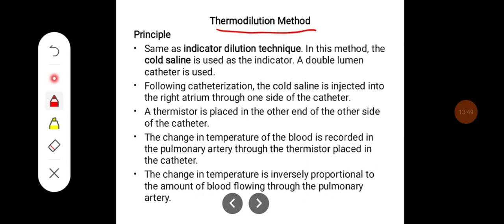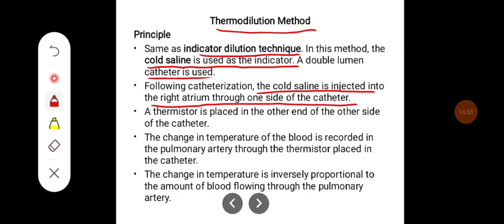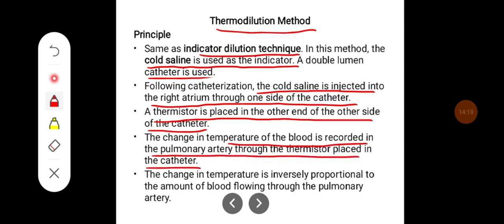The thermodilution method uses the same principle as the indicator dilution technique, but cold saline is used as the indicator. A double-lumen catheter is used. After catheterization, cold saline is injected into the right atrium through one side of the catheter, and a thermistor is placed at the other end. The change in temperature of the blood is recorded in the pulmonary artery through the thermistor. The change in temperature is inversely proportional to the amount of blood flowing through the pulmonary artery.